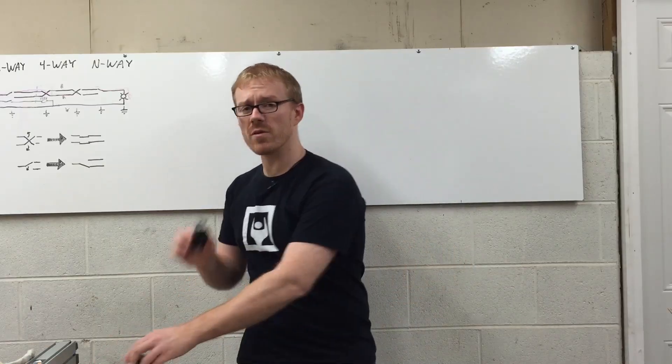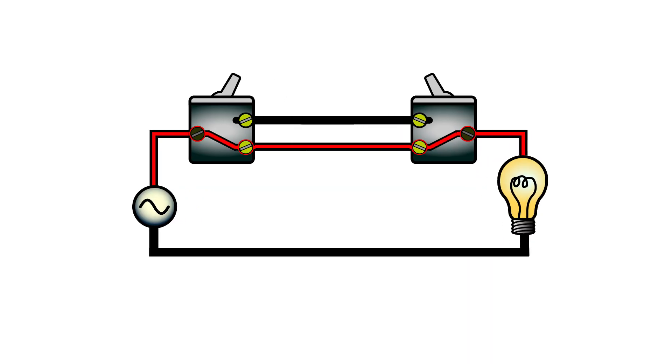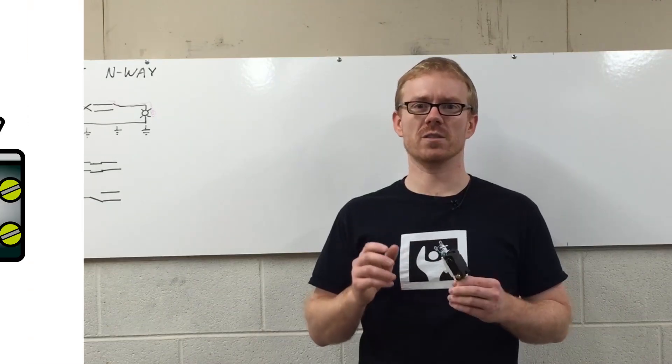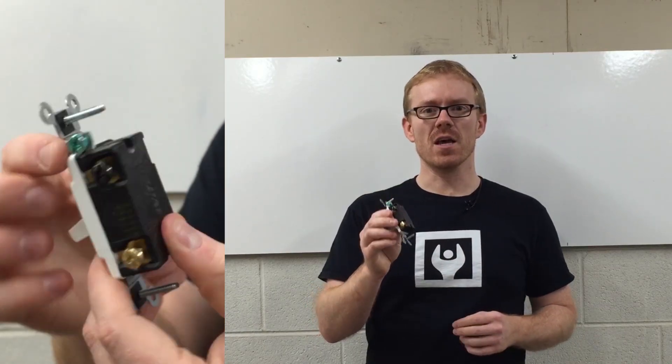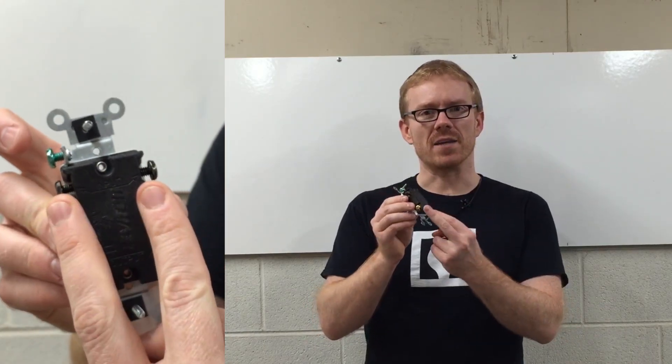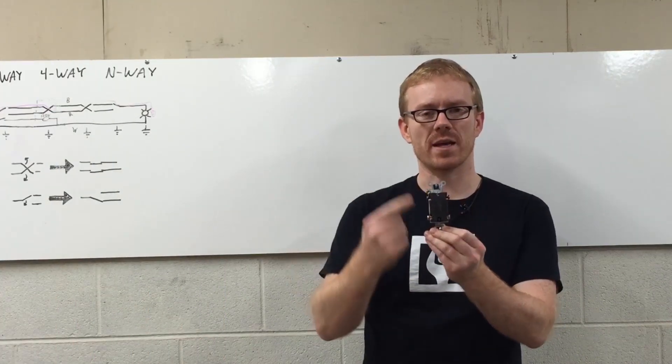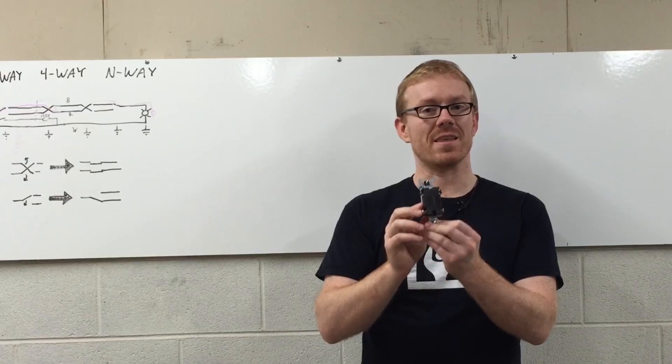The addition of one four-way switch gives you another location from which you can switch the load. A four-way switch works by swapping the connections between the pair of terminals. On the switch that I bought, two of the terminals are black and two of the terminals are gold. With the switch in one configuration, the black terminals are tied directly through to the gold terminals. They go straight through.